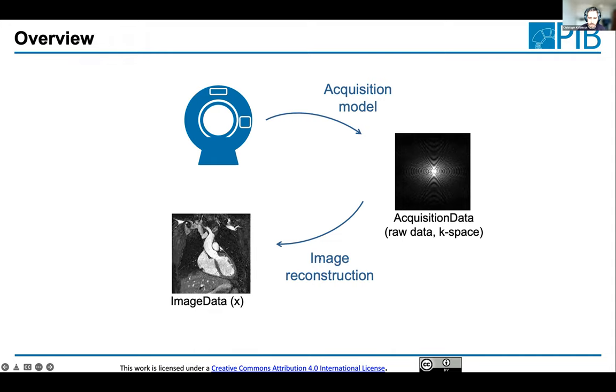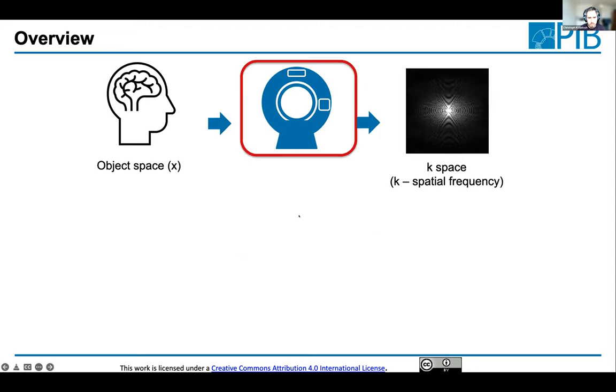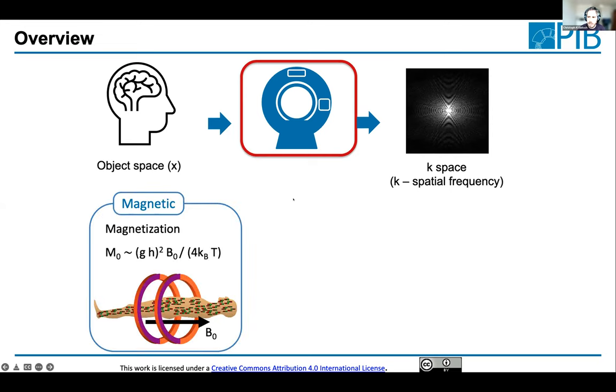You can see a standard T1-weighted image of the heart. The scanner is one big magnet — that's essentially what most of the hardware in there is. We have different field strengths: 1.5 Tesla or 3 Tesla are the common clinical field strengths, with 7 Tesla also available and now CE-labeled for brain imaging. There's also a trend toward lower field strengths, like 0.5 Tesla or even lower, to make MRI available to more people.